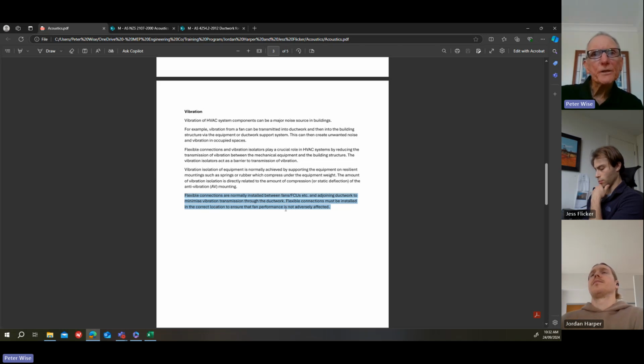But the flexible connections need to be installed in the correct location to ensure that the fan performance is not adversely affected. So what I'm saying there is, particularly for axial fans, if you put a flexible connection at the inlet to an axial fan, that's a problem, because the negative pressure at the fan inlet will pull the flexible connections down and create a disturbance at the inlet, which will cause turbulence and will affect the fan performance.